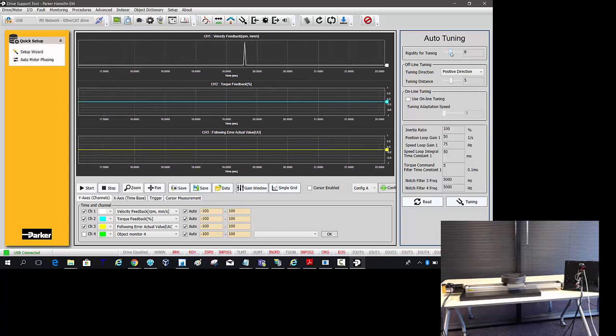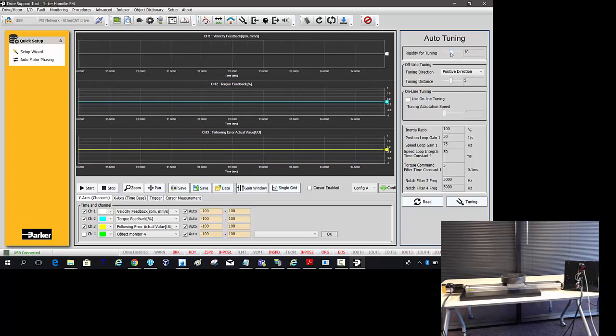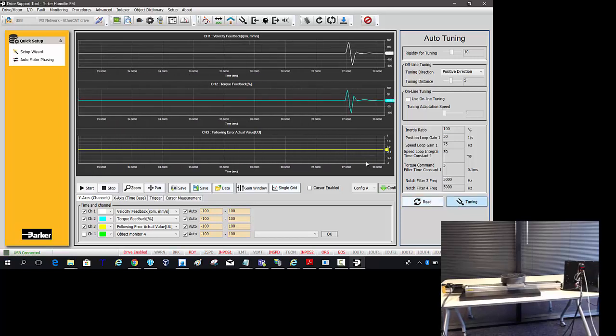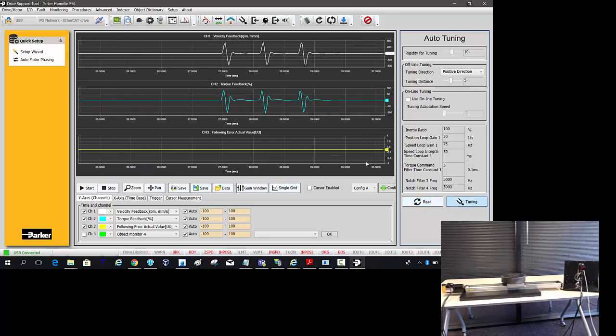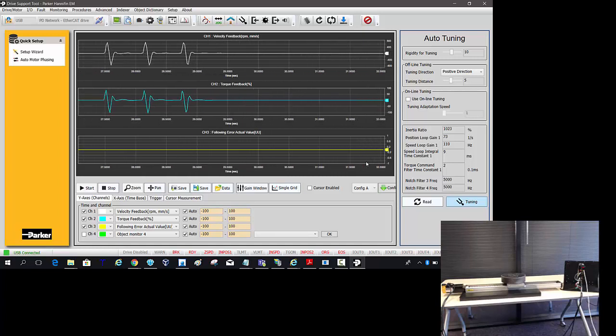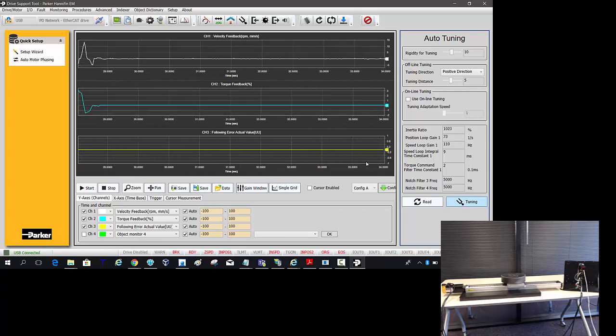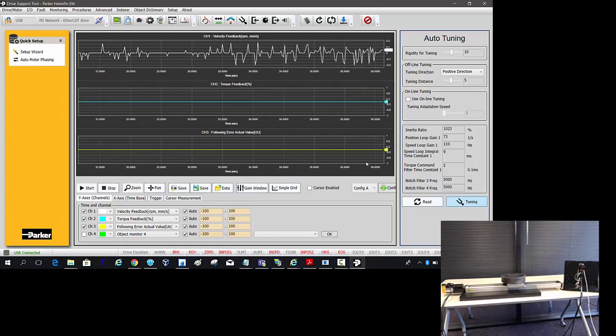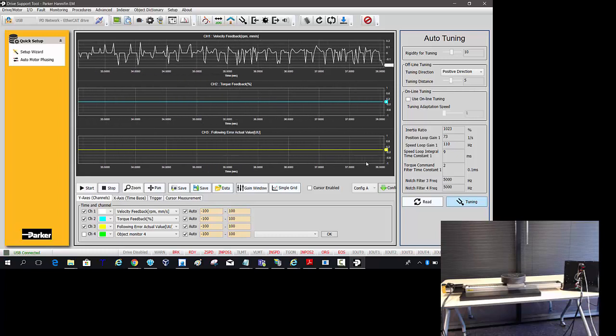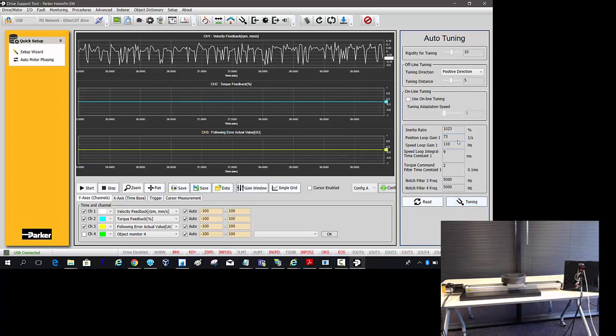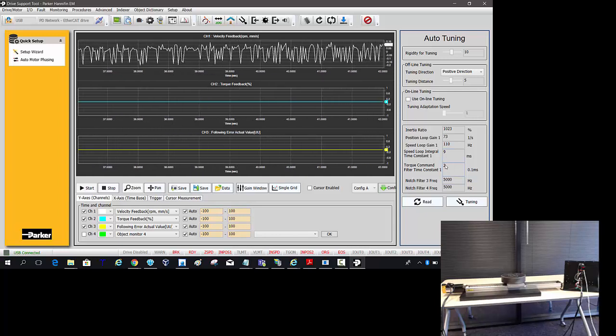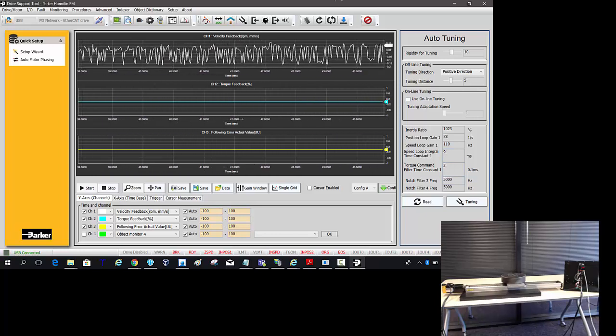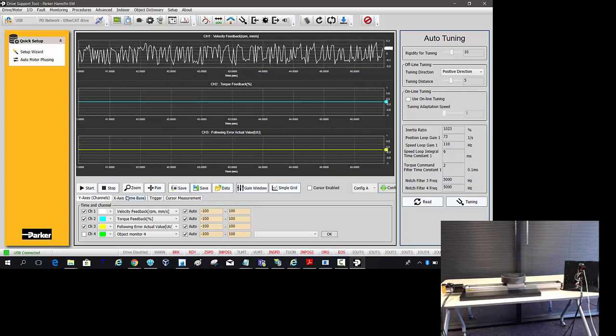And it moves the motor three pulses, and it's trying to detect how much inertia is connected to the motor. So it will automatically adjust the tuning gains based on that. So we've increased the rigidity to 10.